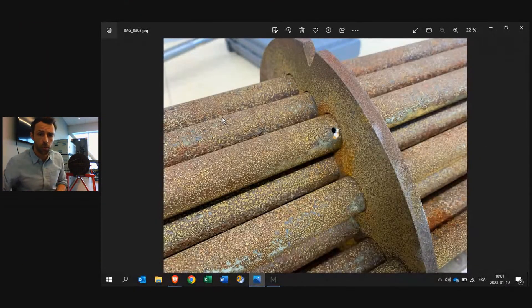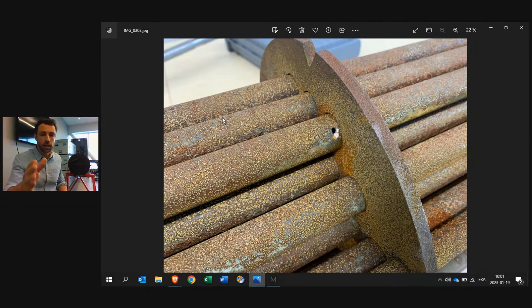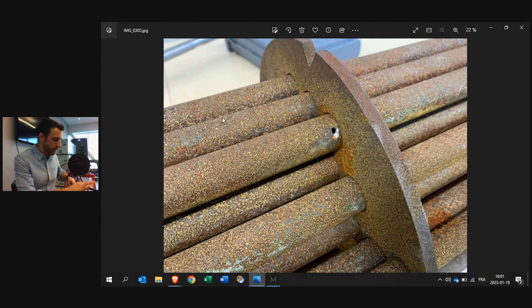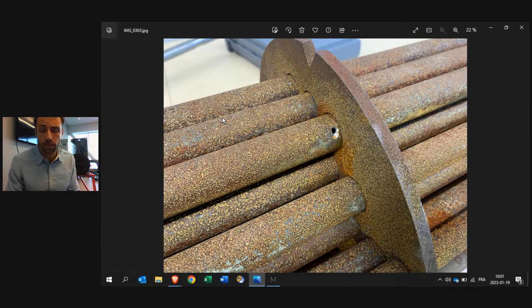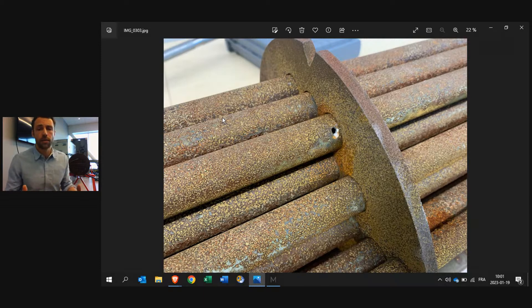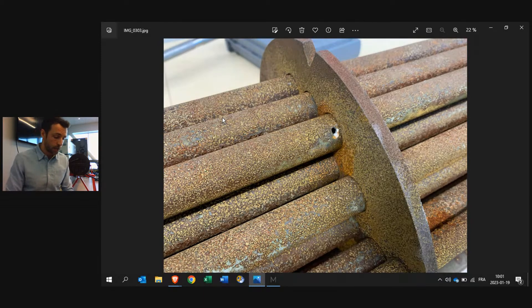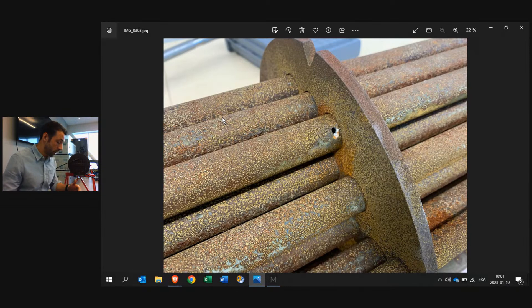What I want to show you this morning is exactly what you see on the picture on the screen — the ability to see defects closer to support plates. In this bundle I have behind me, defects right next to the support plate are the type of indications that are extremely difficult to identify in conventional RFT and are even blinded — this is the blind region where RFT is limited.